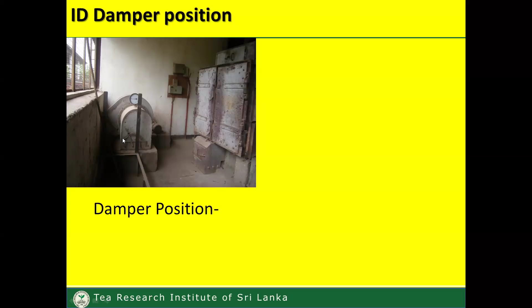If it is more than the required air volume, what will happen? Excess heat can leach through this damper opening, right? So it will facilitate heat losses, and then the firewood consumption of the furnace increases. Therefore, this damper position of the ID fan is really essential, right?